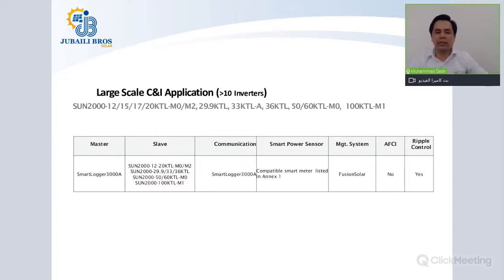For remote monitoring, you will be using the Smart Logger 3000A itself, which is the master device. For the smart power sensor, there is a compatible list given in the next slide, which you can refer to. The management system is FusionSolar. AFCI depends on the inverter models that you are using, but if you are using a mix of all of these, then there is no option. Ripple control is supported by the Smart Logger 3000A, and if your public authority requires it, you can have the ripple control feature as well with the large scale application of C&I inverters.